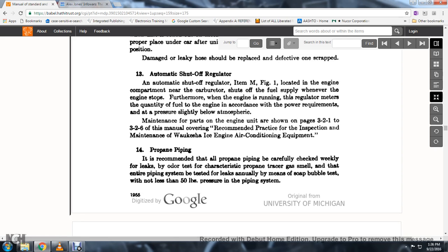13. Automatic shutoff regulator, item M, figure 1: located in the engine compartment near the carburetor; shuts off the fuel supply whenever the engine is stopped. When the engine runs, the regulator meters the quantity of fuel to the engine according to the power requirements, with pressure slightly below atmosphere. Maintenance is part of the engine unit covered in pages 3-2-1 through 3-2-6 of the manual covering standard practice for inspection and maintenance of the Waukesha ice engine air conditioning equipment.